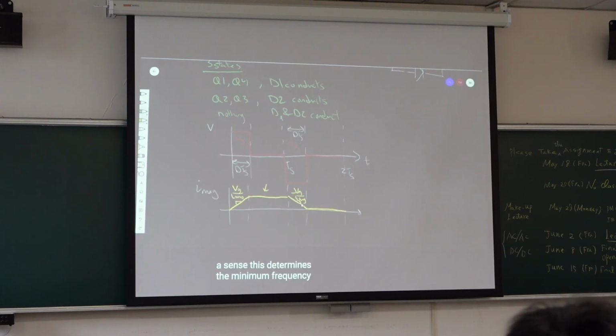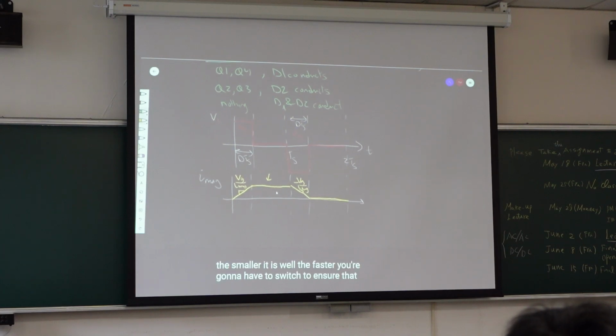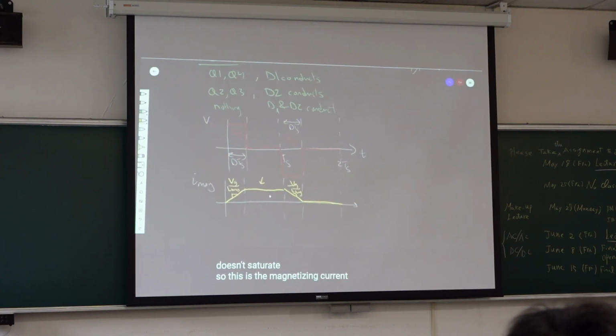If we switch too slow, then this current can get too high. So the size of the transformer kind of determines how fast you have to switch. The larger the transformer, the more core flux it can sustain, meaning the slower you can switch. The smaller it is, the faster you have to switch to ensure it doesn't saturate. So this is the magnetizing current.